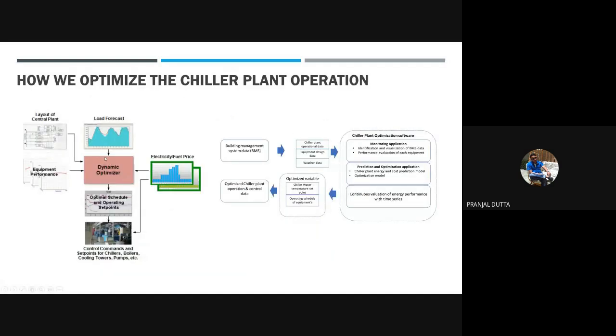So here, this is my input: load forecast. This is the chiller plant load. Then plant layout: I have to prepare a plant layout, how pumps are connected, how chillers are connected, how many cooling towers, whether it is a header system or a distributed system, and the heat exchangers. Even for this particular layout, I have to input all the design data for the chillers and pumps everywhere. For chillers, I have to input design flow, design head, design inlet and outlet temperature, the maximum temperature it can deliver, and the minimum temperature it can deliver.